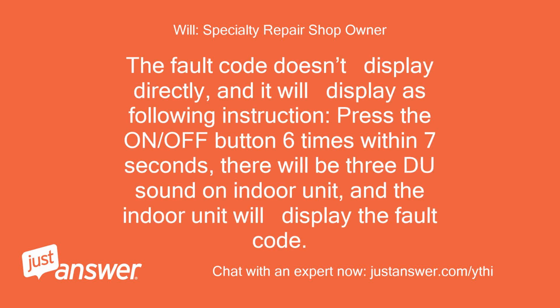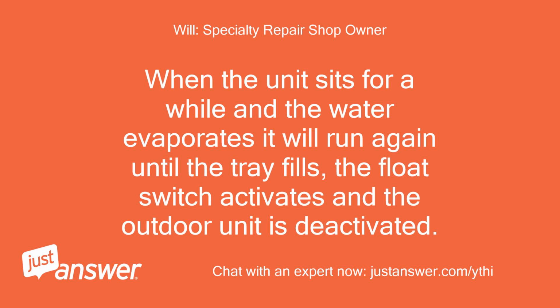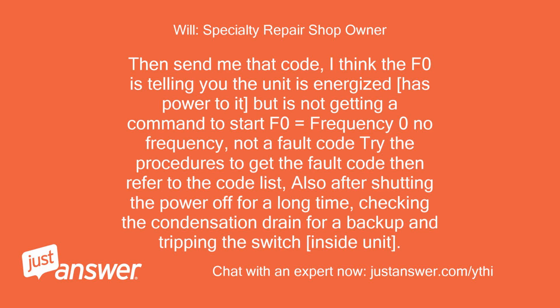The fault code doesn't display directly. It will display following this instruction: press the on/off button 6 times within 7 seconds. There will be 3 beeps from the indoor unit, and the indoor unit will display the fault code. The drain system might be filling up in the indoor unit and causing the unit to turn itself off. When the unit sits for a while and the water evaporates, it will run again until the tray fills, the float switch activates and the outdoor unit is deactivated. Then send me that code.